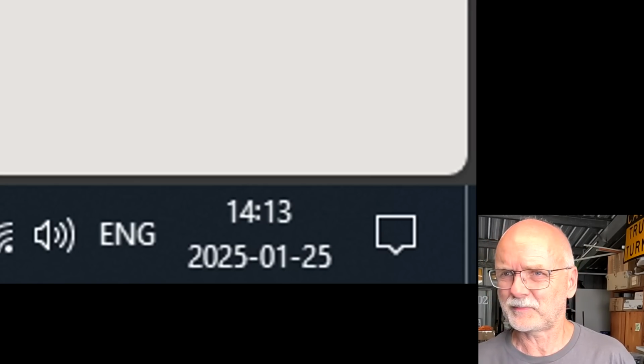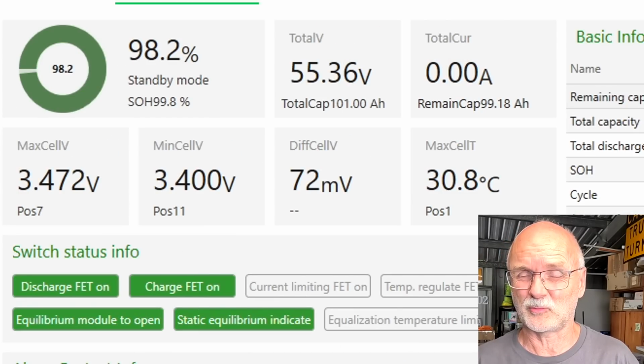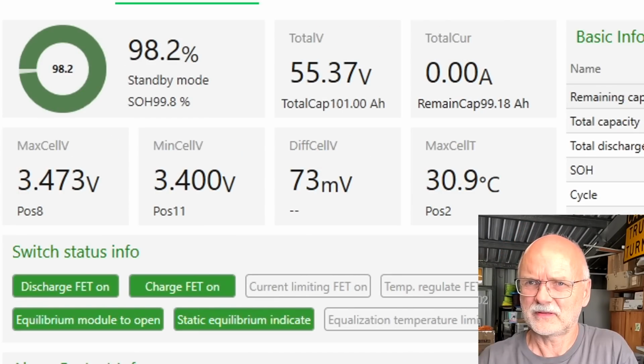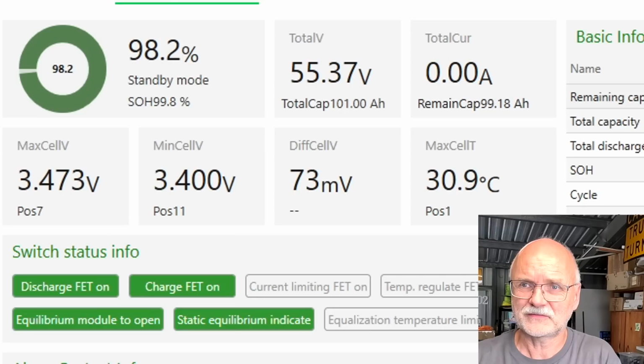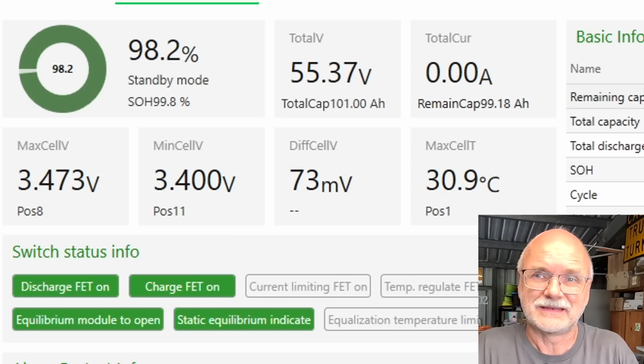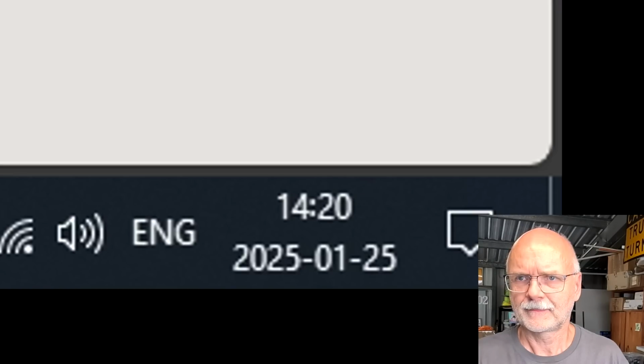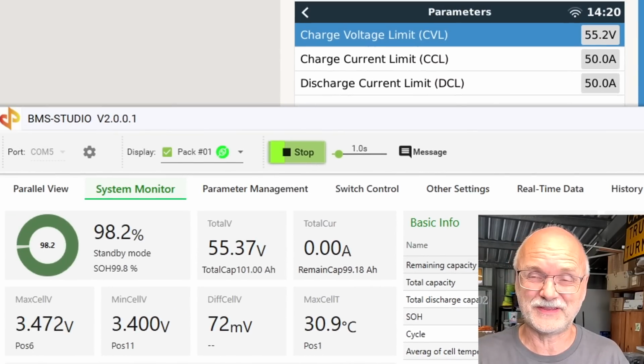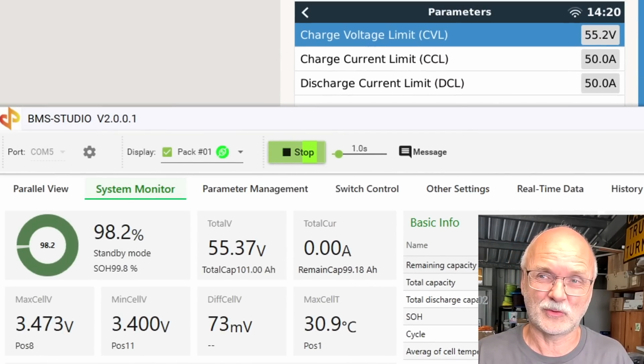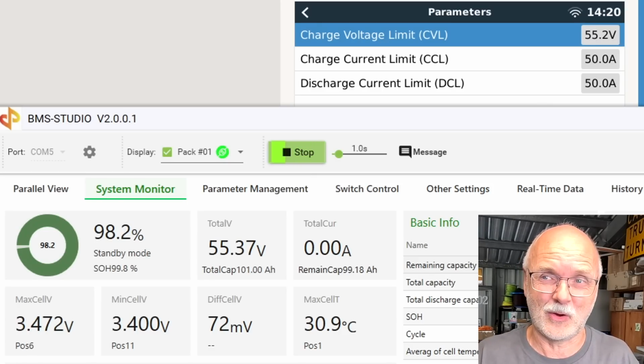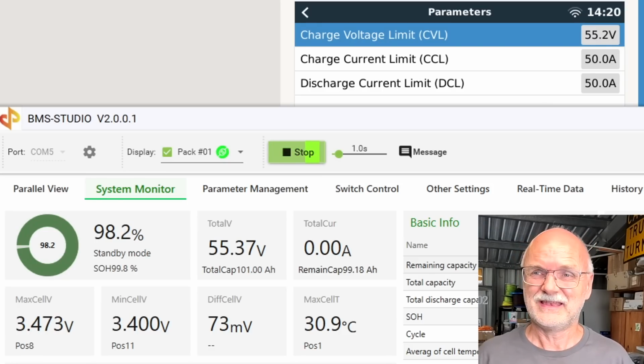Okay, it is now 13 minutes past 2, so we should see the reset in about 1 or 2 minutes. 14 past, 15 past, 16, 17, 18, 19 past, and we have now reached 2:20 p.m., so far over 15 minutes since we hit the 55.2 volts and entered standby mode. There was no charge, no discharge, nothing, but the BMS does not reset to 100%.